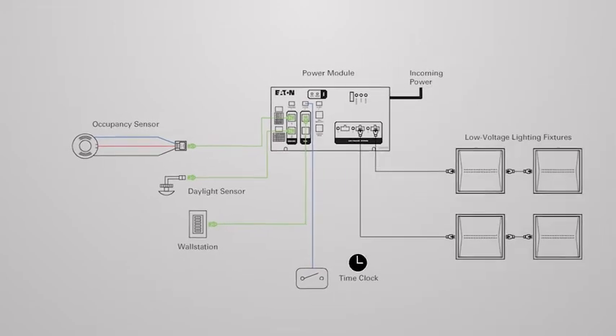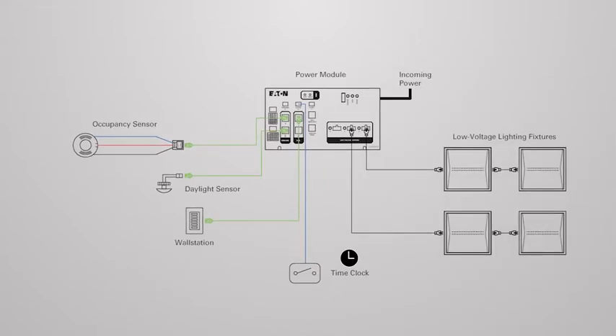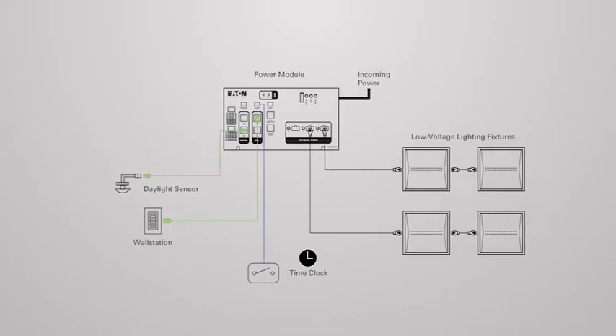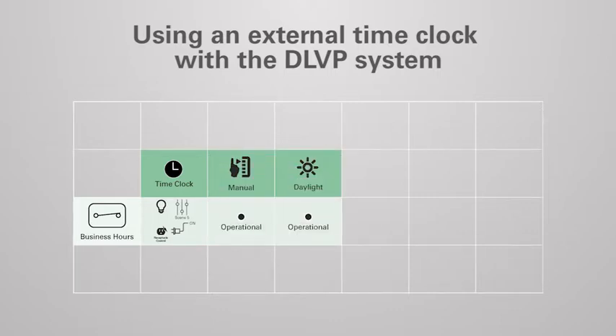How the power module responds to the time clock will depend on if there are occupancy sensors connected to the system. This portion of the video will discuss system behavior when there are no occupancy sensors connected. When the time clock contact closes and the system enters business hours mode, lighting will turn on automatically to user programmable scene number five. Controlled receptacles will also turn on. Manual wall station and automatic daylight controls will be operational to adjust light levels as needed.